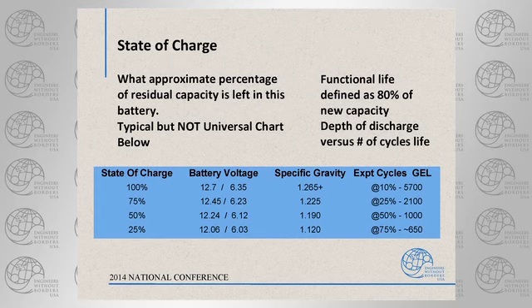But what happens if bad things happen and somebody bypasses the low voltage disconnect, or they leave the switch on overnight and they use a little more capacity of the battery than you intended for them to use? Okay, you use 75% of the battery, now you get 650 charge cycles. So less than 2 years, you've got a battery that's dead. And you go, well, I got a 5-year commitment to the village. You got a problem here.